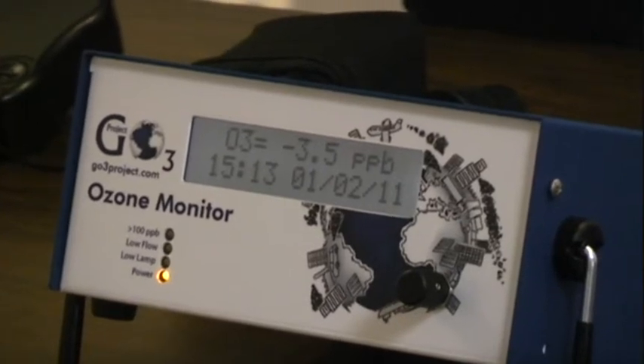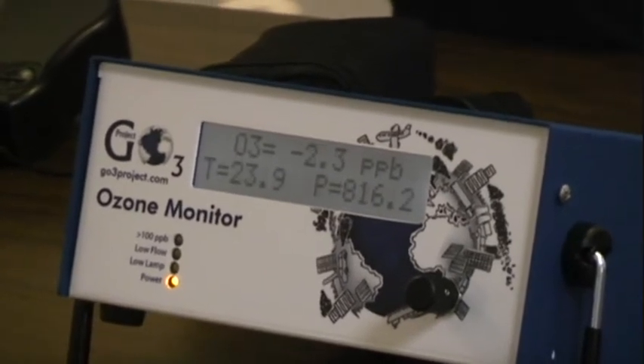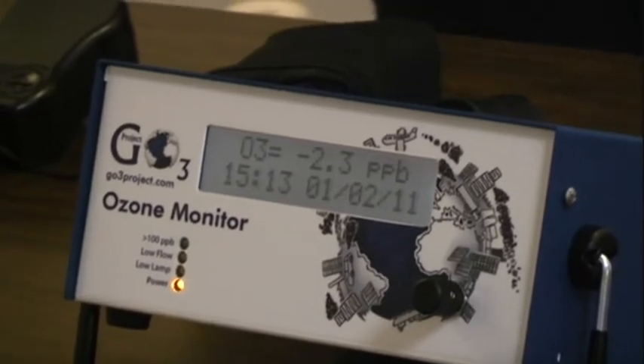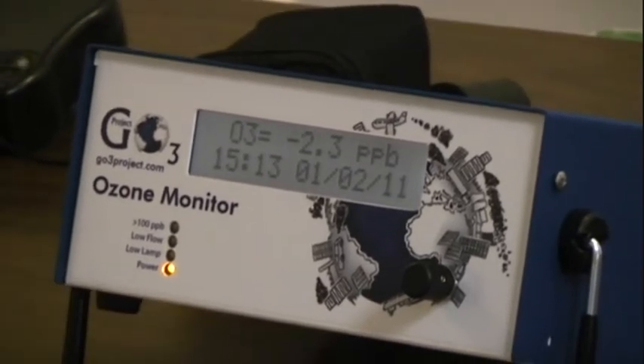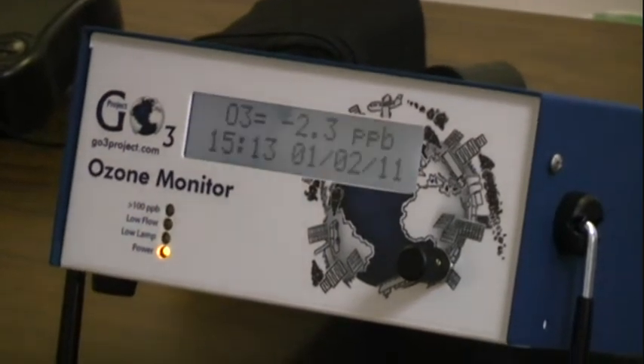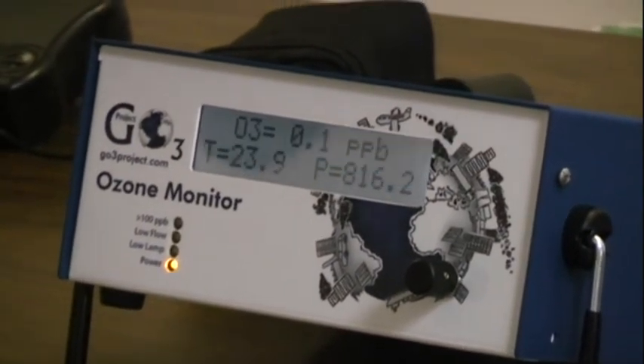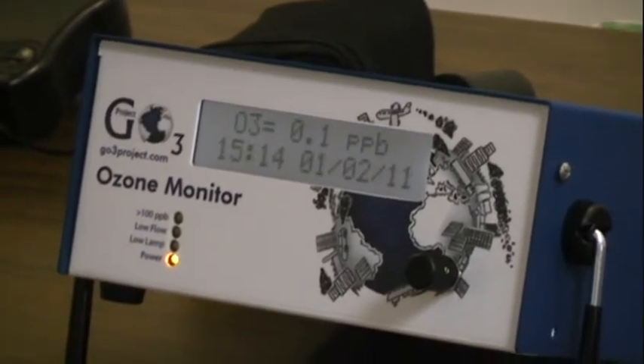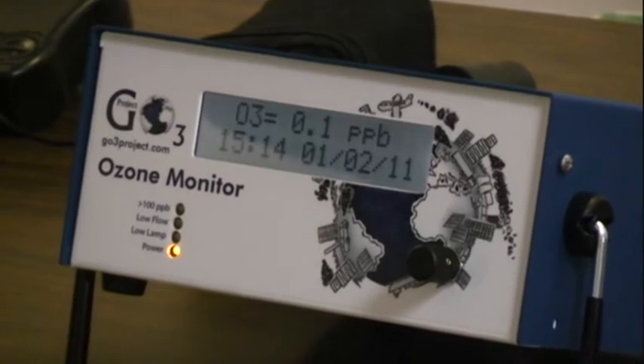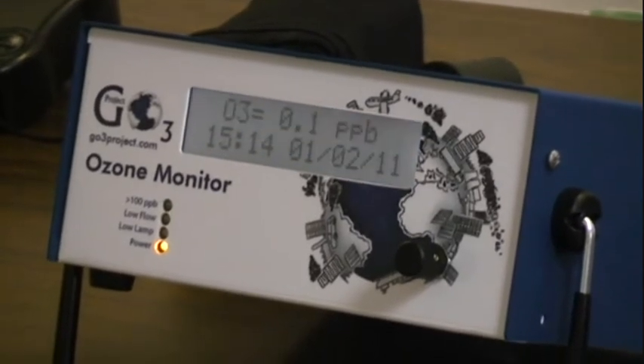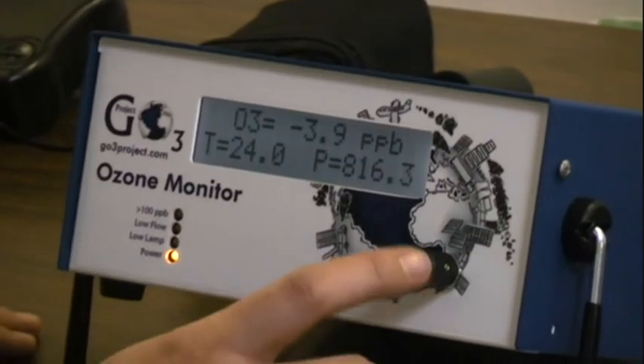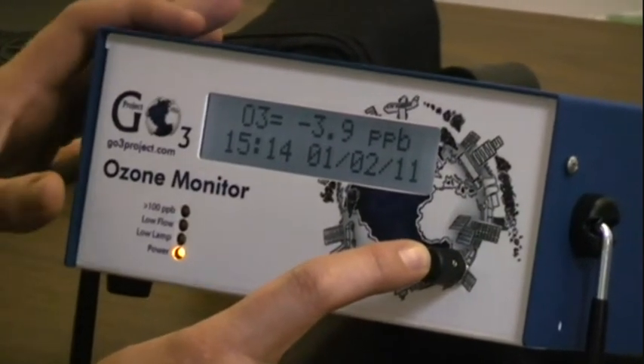Let's say, for example, we have a negative five offset. The average of your readings is about negative five. So what you'll want to do is give it a plus five offset because you're wanting to bring it to zero. The same case applies. Let's say you had a plus five offset, you would need to bring it down five to zero. So that's going to determine what you set your offset.